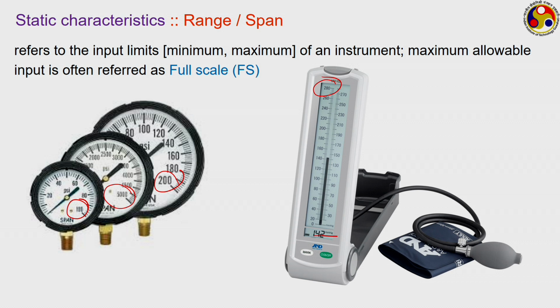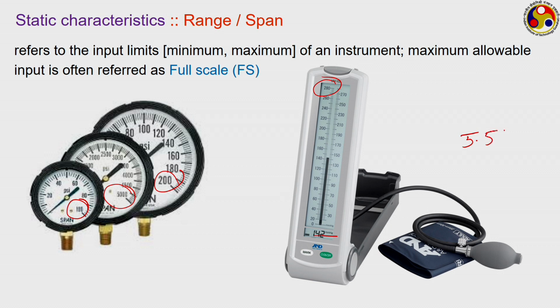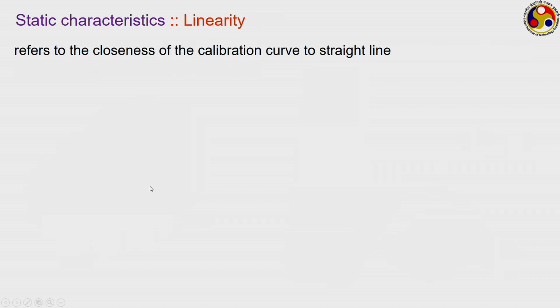Now, 1 millimeter of mercury corresponds to very small psi, or practically 1 psi corresponds to something like 51.7 millimeter of mercury. That means this scale of 280 is actually going to give you only approximately 5.5 psi. That is a much smaller range compared to any one of the three, but we do not need to go for a much larger range when we are measuring the blood pressure. So, this manometer itself is sufficient in this case, sphygmomanometer I should say.